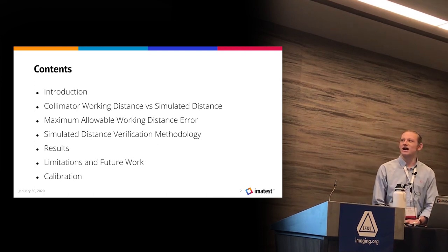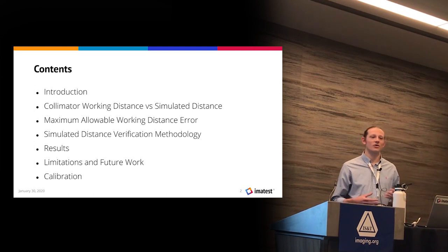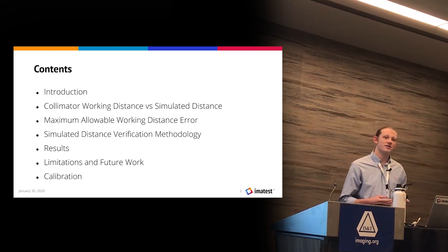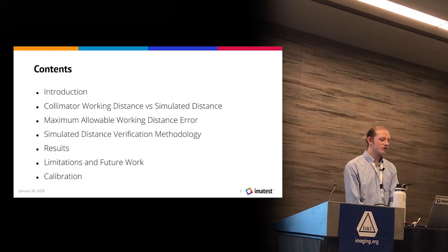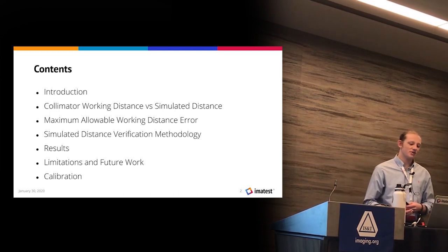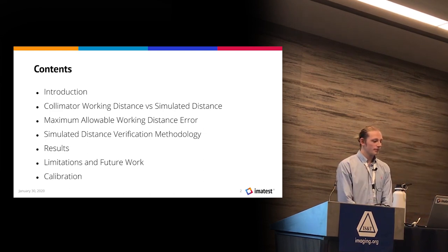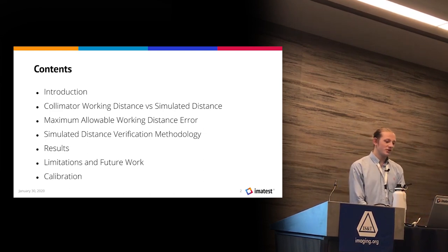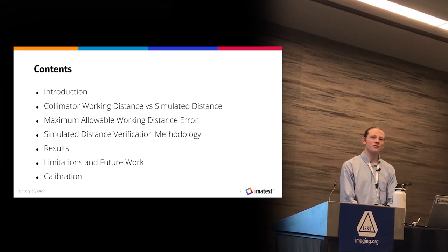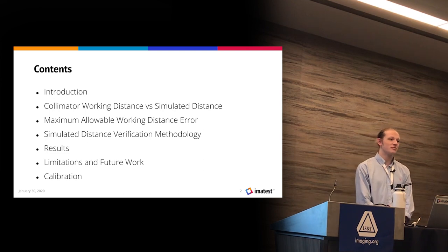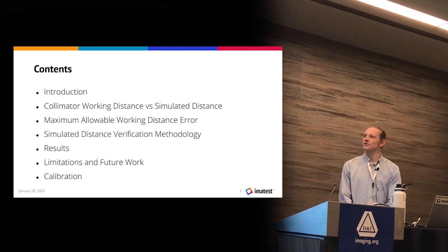I'll then define the maximum allowable working distance error and the relationship between working distance error and the depth of field of an imaging system under test. We've developed working distance error as a metric for evaluating relay lens performance. We have verified the accuracy of simulated distances by comparing the MTF of images captured in the real world with the MTF of images projected at simulated distances through a relay lens.